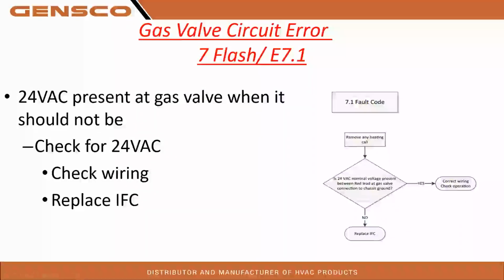Okay, gas valve circuit errors: 24 volt present at the gas valve when it should not be. So this is a very short fault code segment in that book, right? It says remove call for heating. Is 24 volt nominal voltage present between the red lead at the gas valve and the connection to chassis ground? So that's burner ground. If yes, we're going to correct the wiring and check operation. If no, replace the control board, right? So this is a very direct code. It's either the control board or the wiring here, guys.